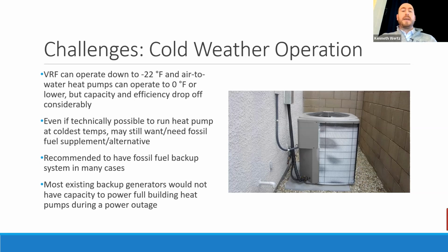And then you've got the added challenge of, what happens if the power goes out? In most cases, the backup generators in your buildings have enough capacity for emergency lighting, a fire pump if you have a fire pump, some basic life safety stuff. And then maybe you've got the hot water pumps and the boiler on the generator. But that's a much smaller load than what it would take to run a building's worth of heat pumps, or even a limited amount of the building on heat pumps, just to keep things from going into an unsafe state.